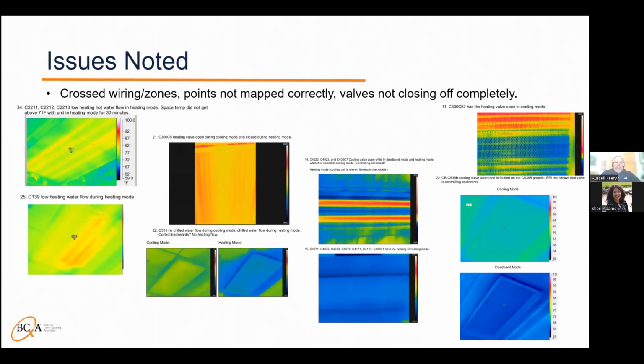heating mode, they weren't actually getting adequate heating. They had an issue with the valve on that particular one. And then the one right below it was in heating mode, it wasn't really flowing like it should. So again, it would be hard to tell that that system's not functioning. And in a couple of these arrangements, the way they were set up is they had 3 beams in a space. So they were maintaining temperature in the space based on the BAS controls. But when you were doing the individual beams, we had instances where the beam in the middle was not functioning, but the other 2 beams were still keeping the space comfortable. And it wasn't known that that's what the issue was.